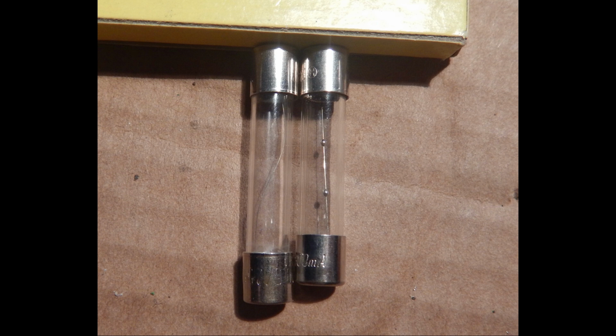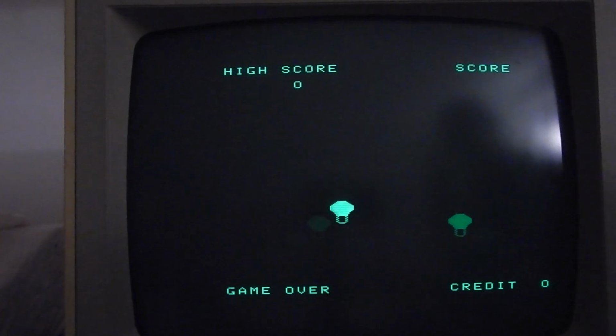Long story short, tracing the connection from the power transformer secondary showed no continuity across the fuse holder. The fuse inside was not blown, but for some reason is shorter than the correct size that fits in that holder, so the fuse was replaced with one tall enough.